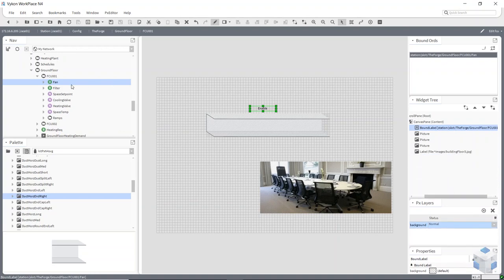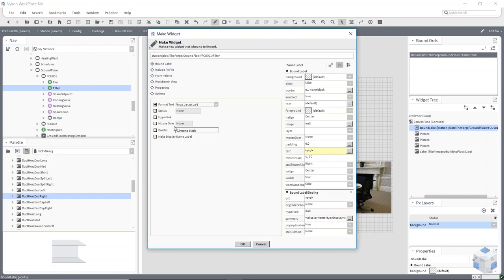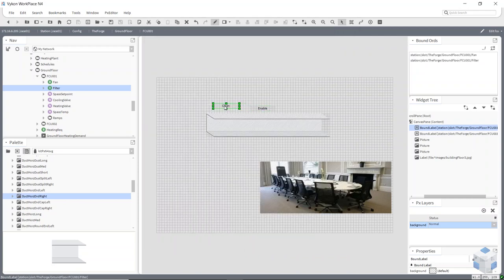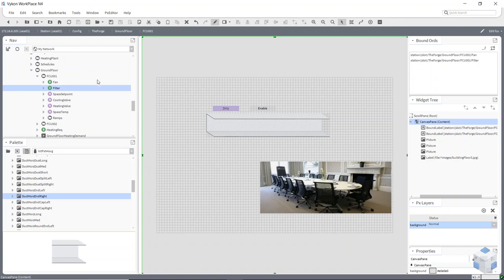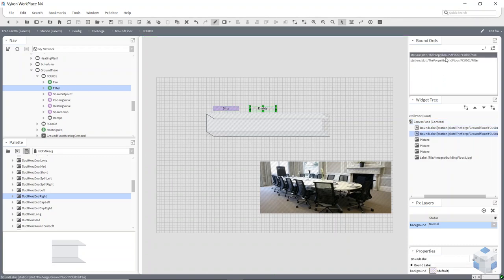Now I'll add my filter using the out value. The status option shows colors attached to that component — if there's an alarm you can have red, orange, or any workbench colors come through. If you choose Color and Blink, it will blink until the alarm is acknowledged. Once acknowledged it will still be red if still in alarm, but won't be blinking. I'll choose Color — here's my filter status. If I right-click and override it to Active, you can see it's gone purple.